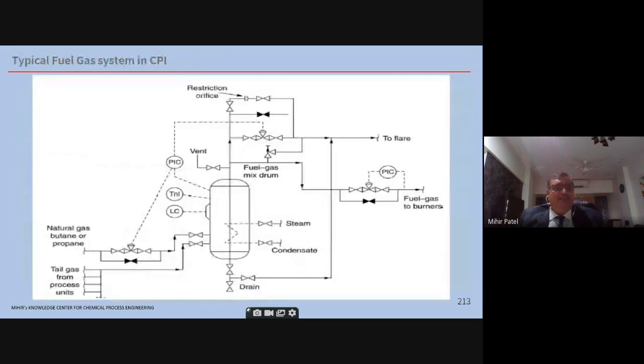Now a typical fuel gas system. Wherever you have fuel gas, you are firing in burners. This fuel gas may have condensations. For example, you have pentane, hexane. These types of fluids may condense out. So you don't want two-phase going into the burners. If you have two-phase going into the burners, that's not good. You'll have a fireball occurring. You may damage the internals of the fire heater.